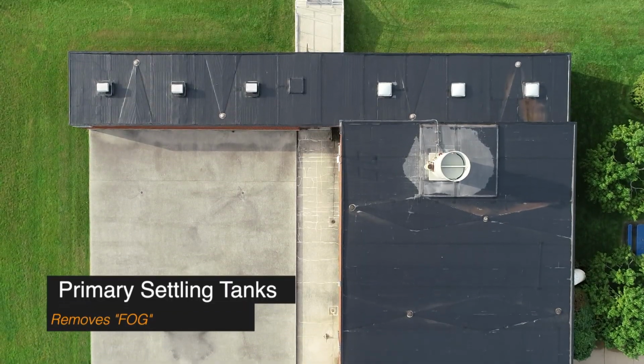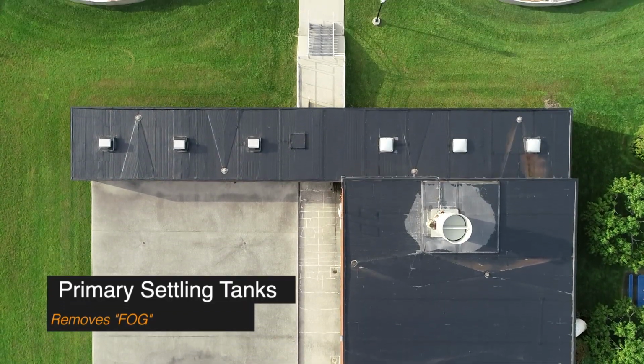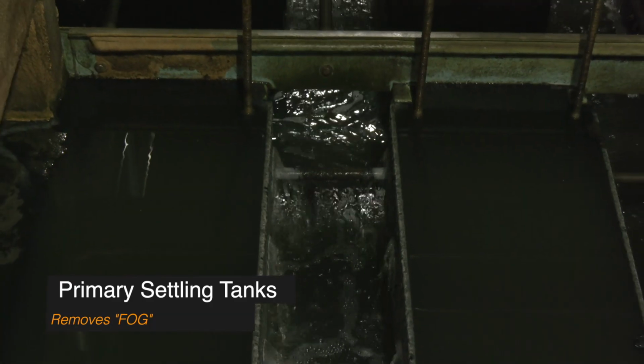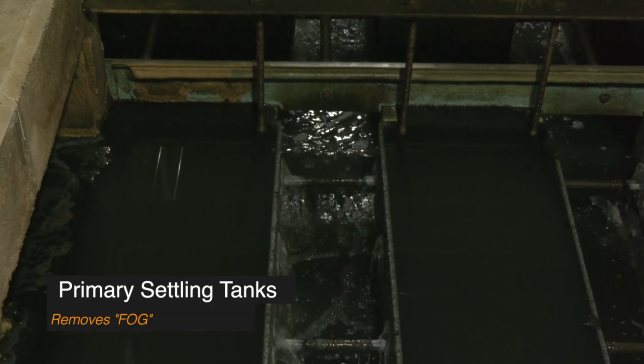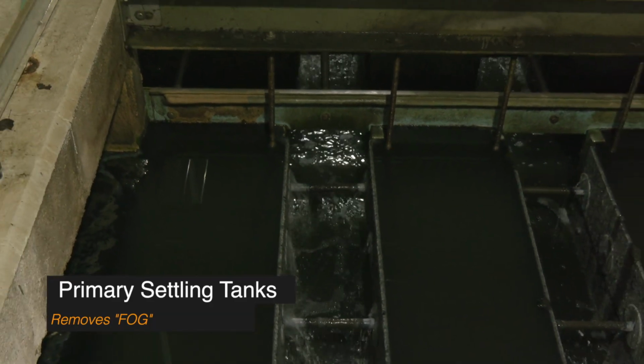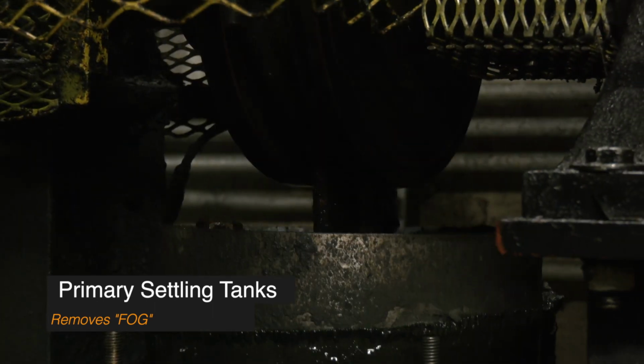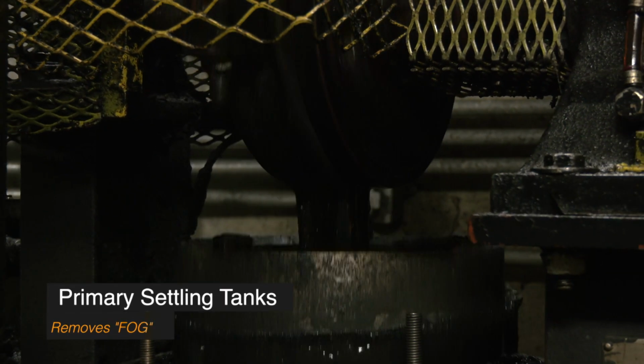Here we slow the water down to about 1/2 foot per second. This allows the fine particle suspended solids to settle at the bottom of the tank to form a sludge. Fats, oils, and grease, what we call fog, rises to the surface. The fog is skimmed off the top of the tanks and the sludge is pumped out of the tanks to a digester system for further treatment.